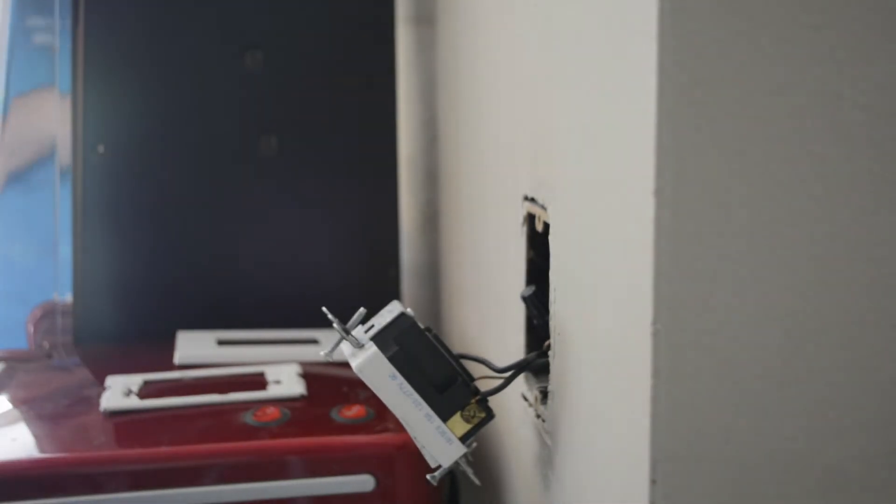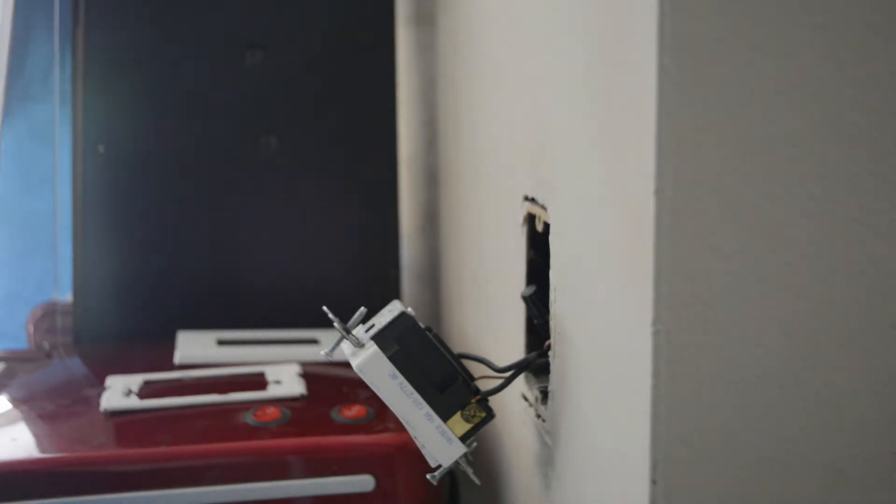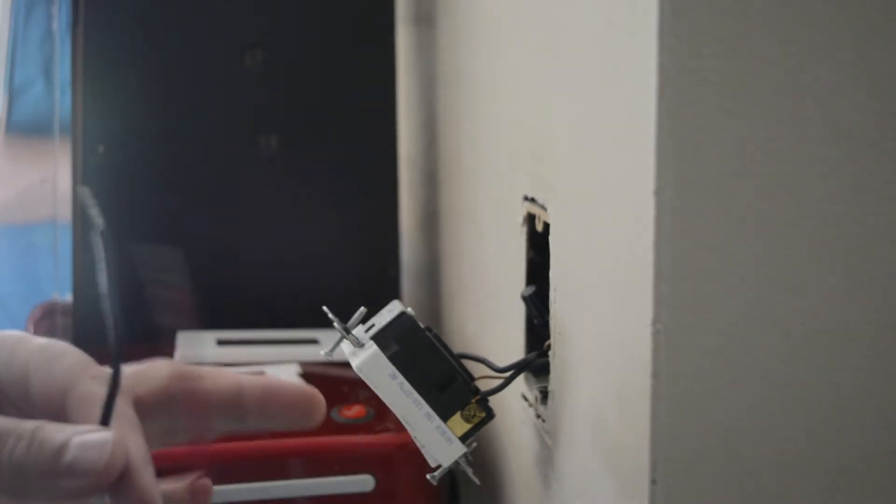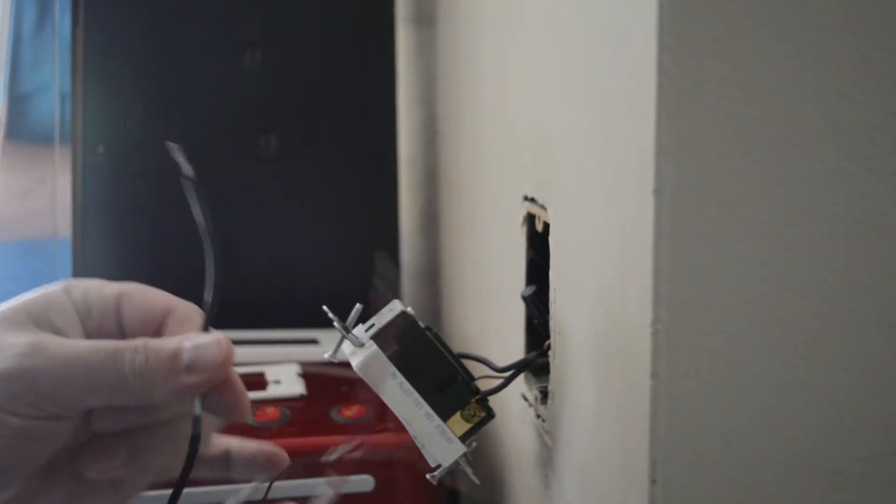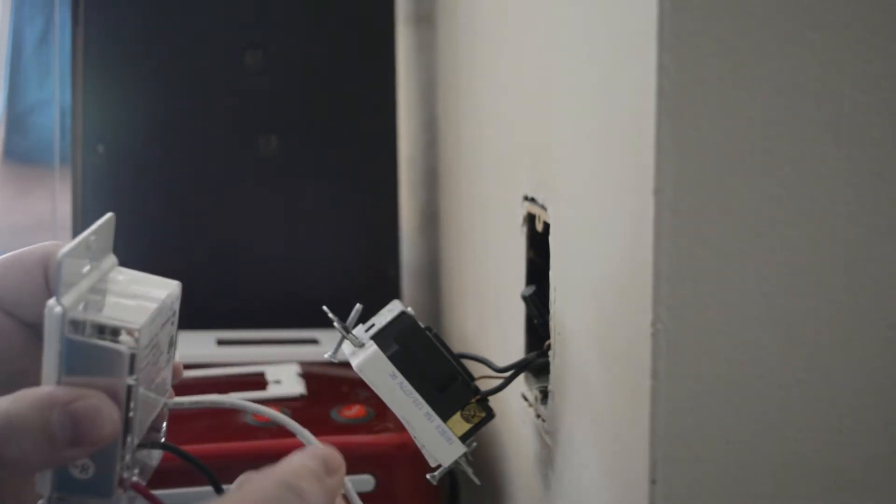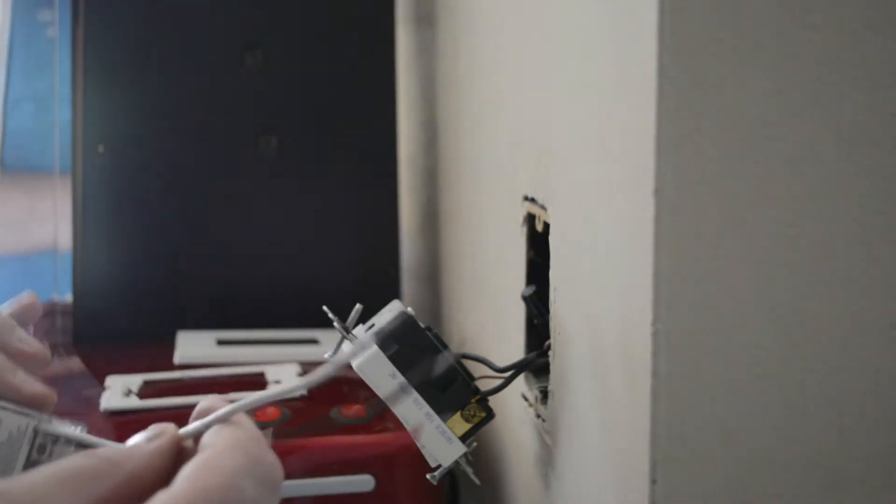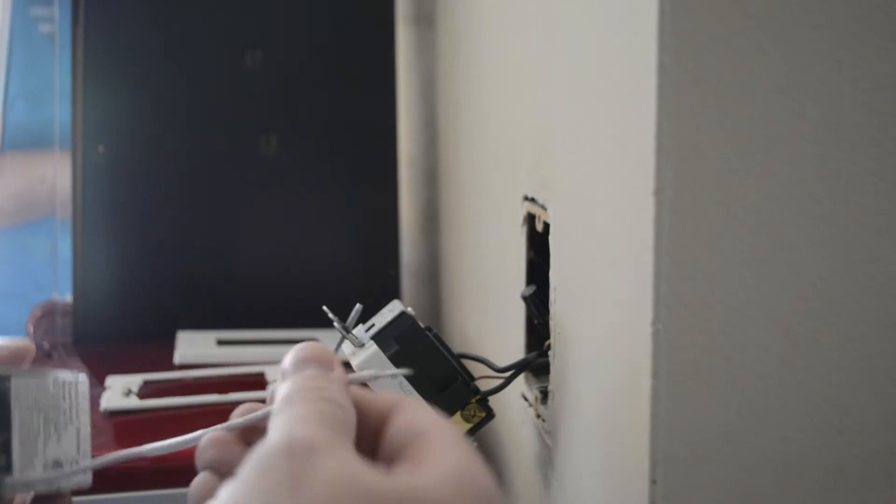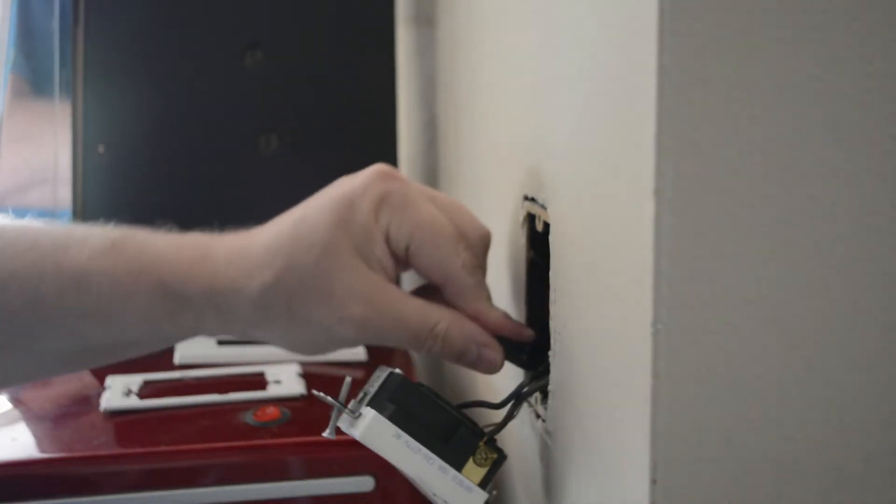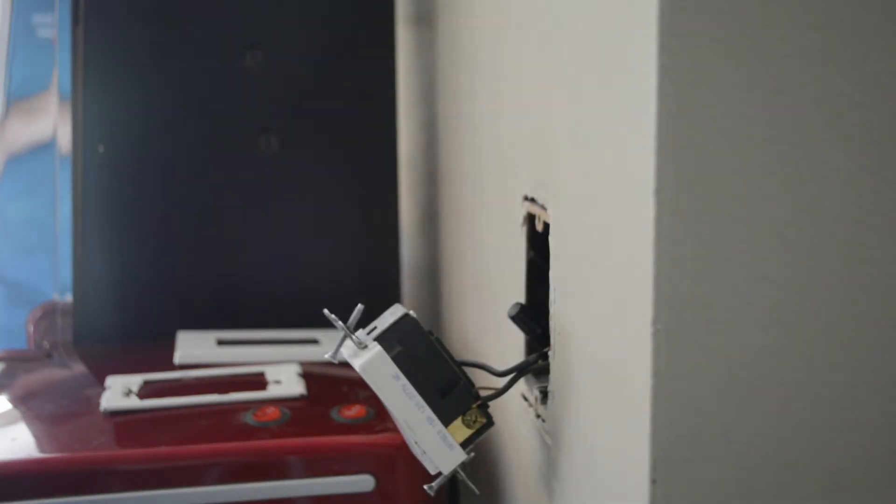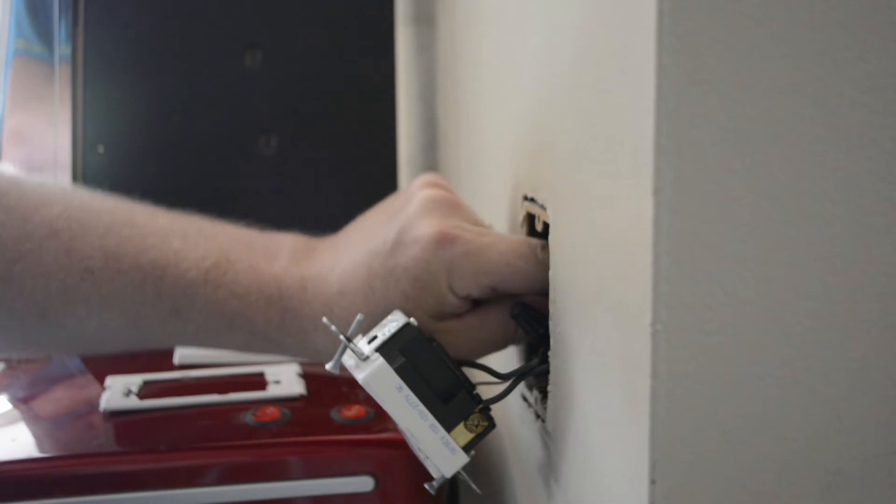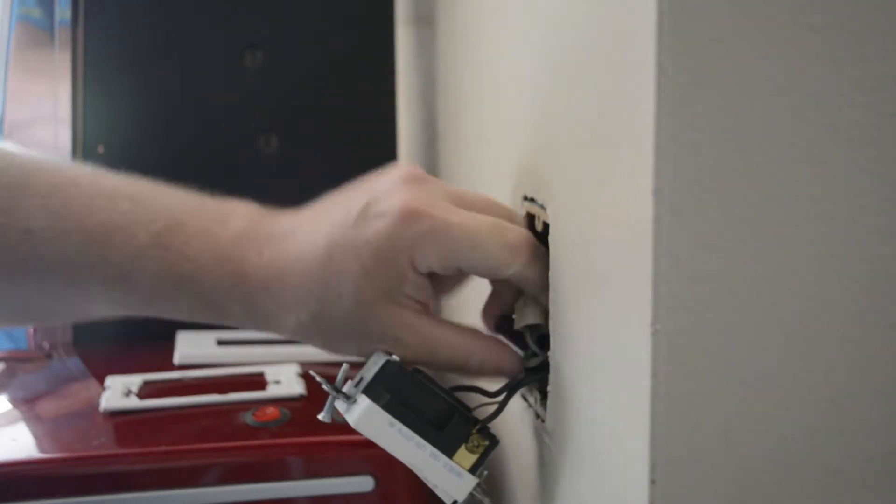Now, for Insteon switches, we need there to be a neutral wire in the box. So, regular switch, you have what's called the line, which is the wire that provides power and then we have load, which is the wire that goes to the light. But for Insteon to be powered up, we're also going to need this neutral wire. So, what you're looking for in the box is a set of white wires that are wire-nutted together.